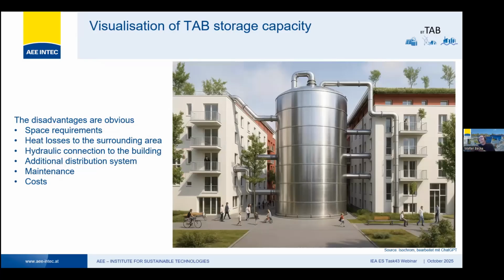This results in quite a few disadvantages listed on the left side. Basically, you need a lot of room to put the storage somewhere. You have quite a few heat losses, especially in summer, going to the surroundings where you cannot use them. You still need hydraulic connections to all the buildings, and you need heaters or a heat and cold distribution system in addition to the tank in the building. You have maintenance for everything, and it also costs extra because you have to build the tank.